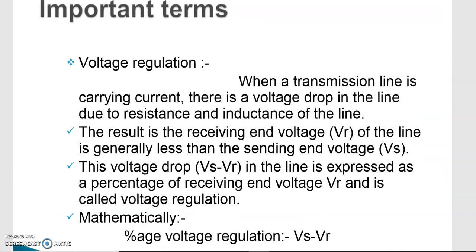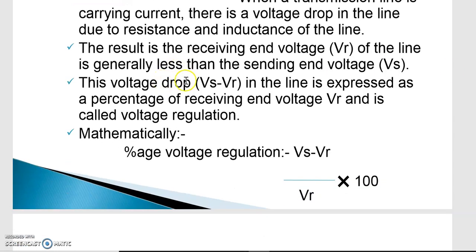Now we have to talk about important terms during modeling of a transmission line. First is voltage regulation. When a transmission line is carrying current, there is a voltage drop in the line due to resistance and inductance. The receiving end voltage Vr is generally less than the sending end voltage Vs. This voltage drop — sending end voltage minus receiving end voltage — expressed as a percentage of receiving end voltage Vr, is called voltage regulation. The formula is: Voltage Regulation = (Vs − Vr) / Vr × 100.